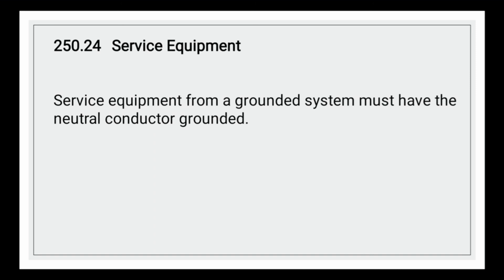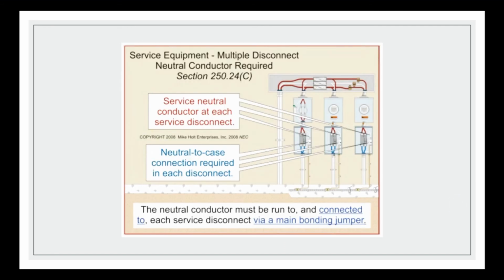Okay, in Article 250 Section 24 about service equipment. Service equipment from a grounded system must have the neutral conductor grounded. Okay, this is the application. The application is about multiple disconnects: a neutral conductor is required. We must install the service neutral conductor at each service disconnect. Okay, we also have to install the neutral-to-case connection at each disconnect. The neutral conductor must be run to and connected to each service disconnect via a main bonding jumper.